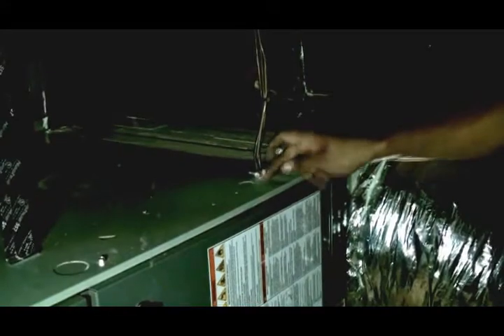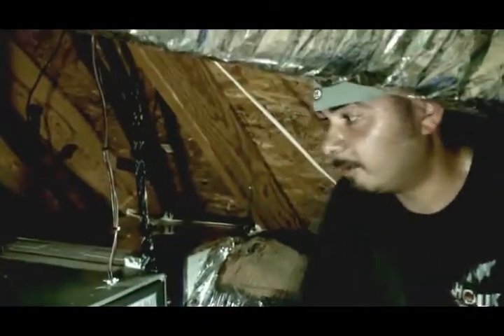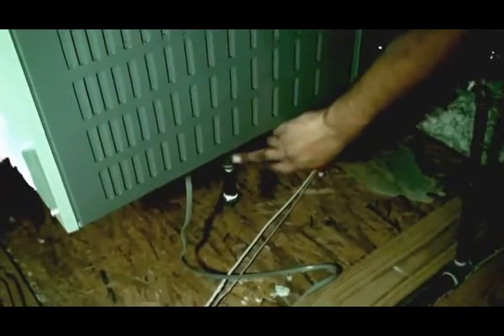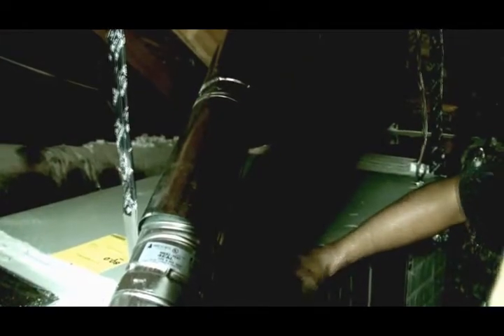As opposed to the other system, we install Romex connectors to protect this wire from any vibration so it won't fray or anything like that. New metal straps supported throughout the whole system to help it keep level, and also to help out with vibration. We do new flex lines with the system on the gas line, and we install every system with the sediment trap, which helps out when we do service and maintenance. Usually maintenance will take this cap off and clean that out, and if there's any debris in there, we'll know that something's going on with the gas lines here, having too much debris or anything like that. Same thing with the high voltage. We do a Romex connector down there and make sure it's protected so it won't fray or anything like that from any vibration. If you notice also, we have 1-inch clearance on flue pipe. There's nothing close by it, for any fire hazards or anything like that. We make sure that that's nice and secure.